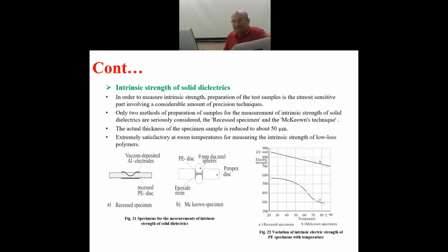I mean, the field conditions, the voltage, and this is normally given in kV per millimeter of the peak value. Normally, it should be given in peak value, as I said, because the breakdown always takes place at the peak value of the voltage.